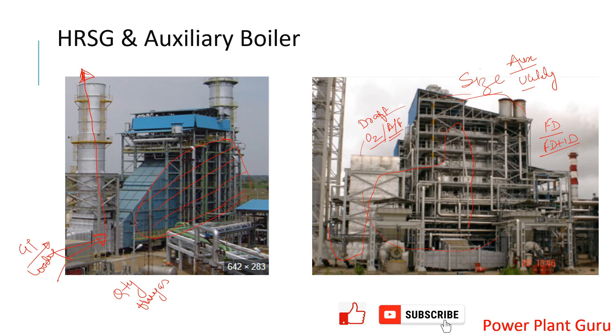Another point is that in the HRSG, steam generation is totally dependent upon gas turbine loading. However, there may be supplementary firing — in-line burners in line with the flue gas coming from the gas turbine. Running these additional fuel-fired burners gives two benefits: one is an increase in steam quantity, and another is control of steam temperature. Many times without supplementary firing you lose temperature and steam temperature goes down, so supplementary firing gives you that level of control.